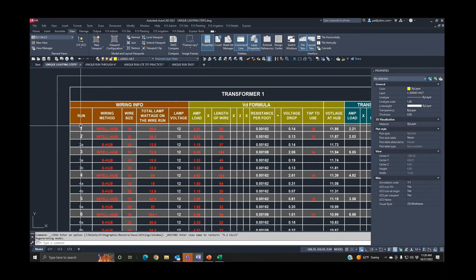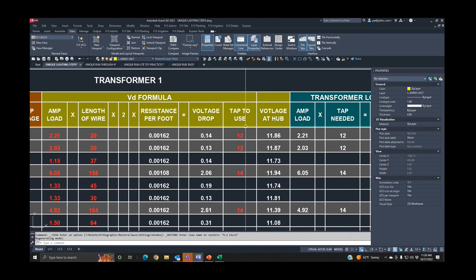Once we have these calcs, we'll jump out to an Excel spreadsheet and run one for each transformer on the project. We're going to dig into the spreadsheets a little later this morning, but the thing I want to point out is that this information tells us on transformer number 1, our first run, we need to use a wire size of 12, and we need to connect it into our 12 tap.